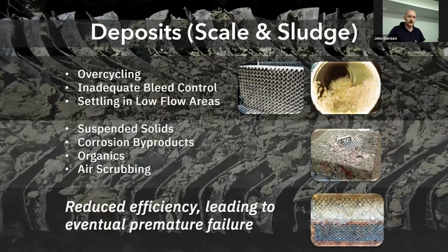So even an otherwise well-controlled system from a bulk water standpoint might have problems because there are low flow areas where things are settling out. You also have suspended solids. Suspended solids can come into the system from the outside air because cooling towers are really good air scrubbers. So you can have pollen, leaves, insects, all kinds of things, construction debris coming from the environment, road exhaust, getting scrubbed into the tower and then draining into the bulk water, and then causing deposits in that way or clogging up strainers. All these things add up to reduced efficiency.